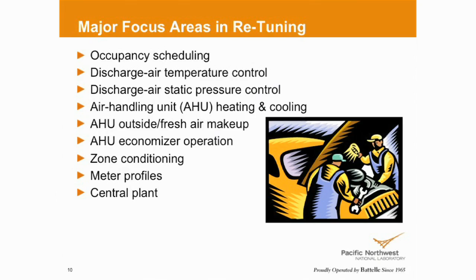And then the last area we want to focus on is central plant. A lot of organizations, like some of yours, have central plants - whether it's hot water, steam, or chill water. And how are those operating? Are they operating efficiently? Are there times of the year when they could be shut down? We still emphasize shutting down chill water plants if they're not needed in the middle of winter, and hot water/steam plants if they're not needed in the middle of summer.